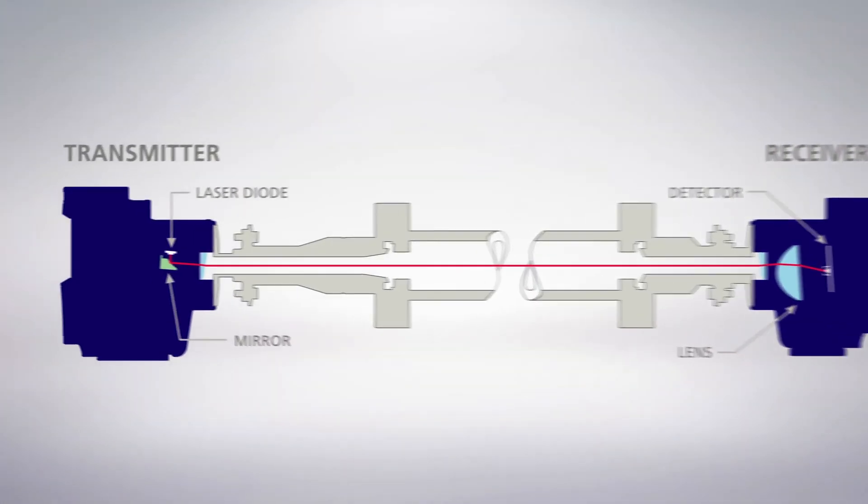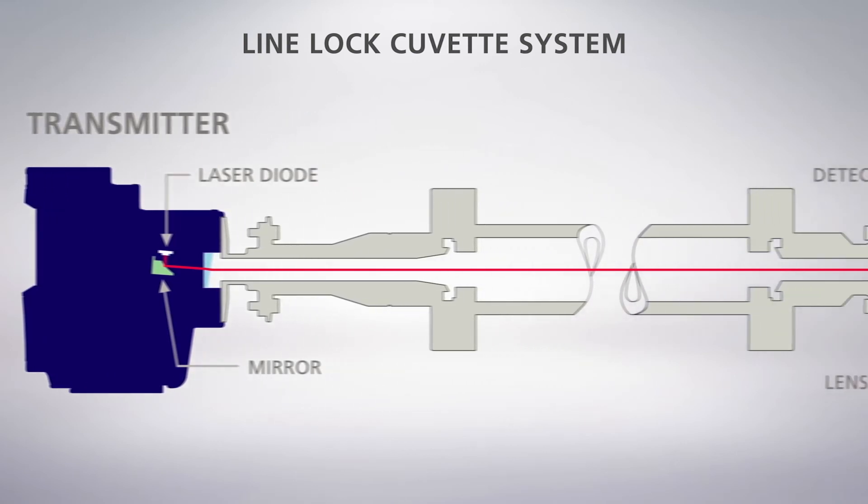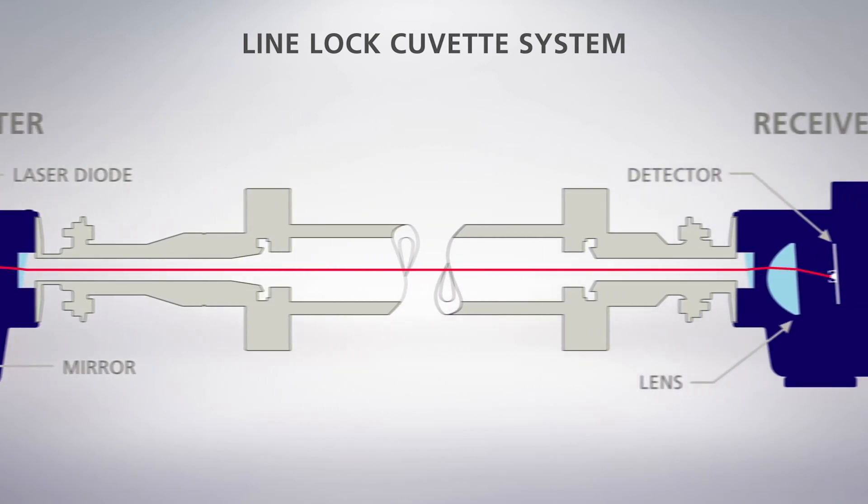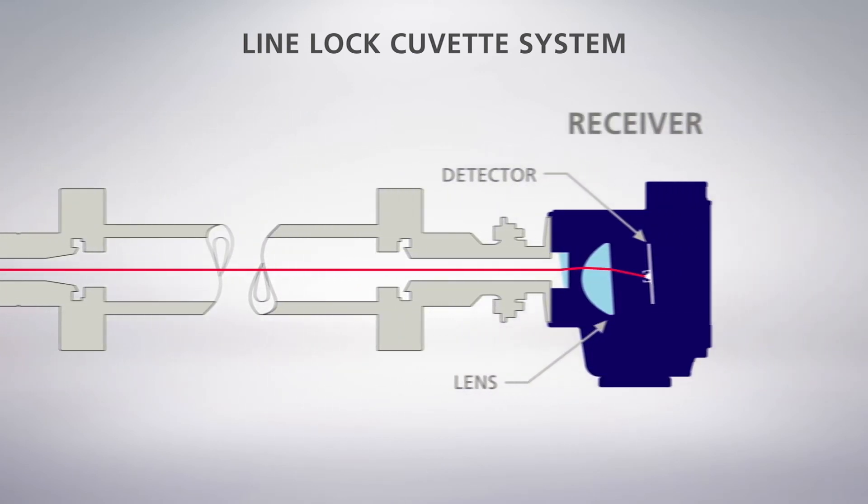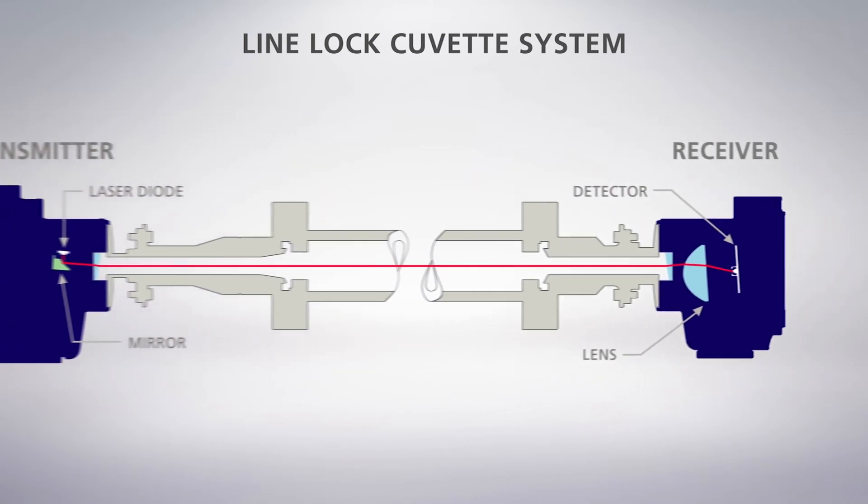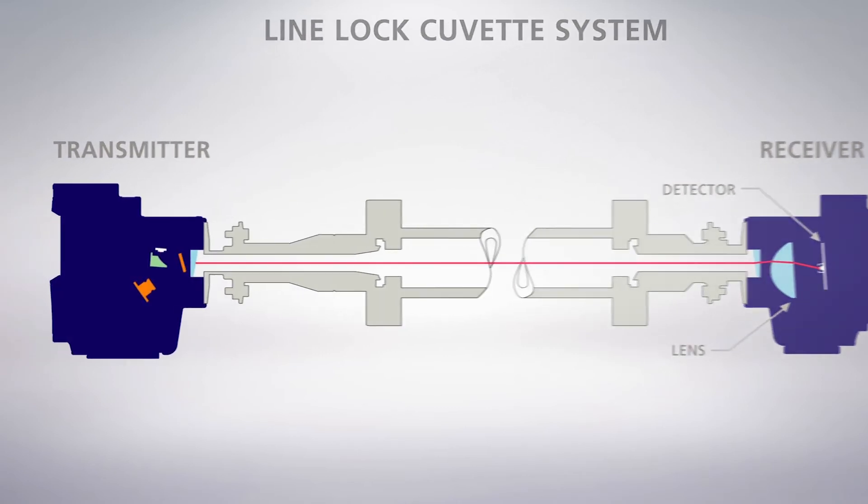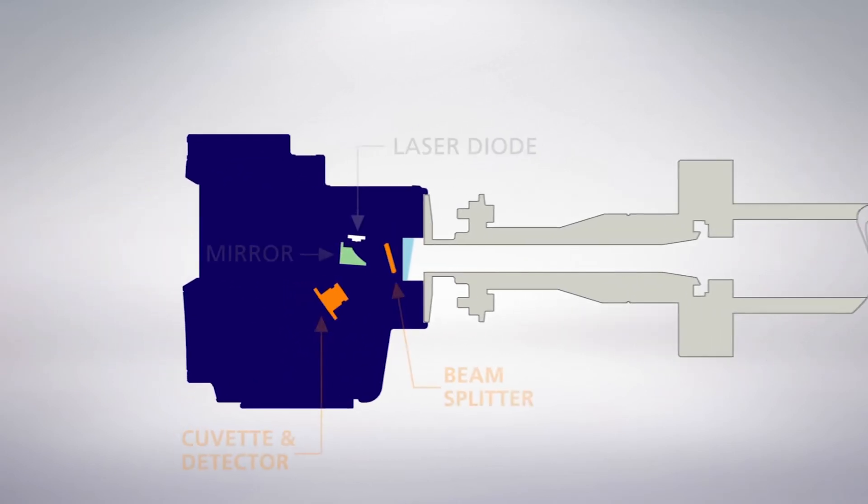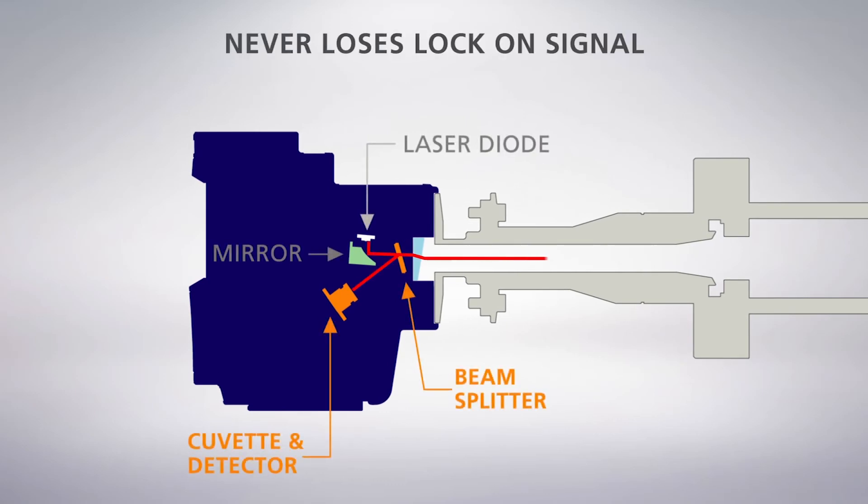While traditional TDL analysis uses signal line lock via less stable water lines, the Laser 3 Plus uses Servomex's unique line lock cuvette system. This provides an absolute signal reference for ammonia, so it never loses its lock on the ammonia reading, providing the most stable measurement at all times.